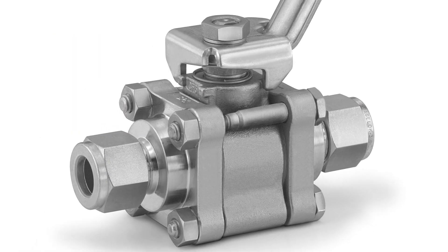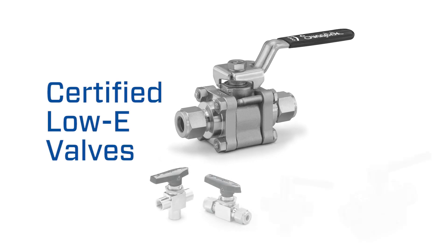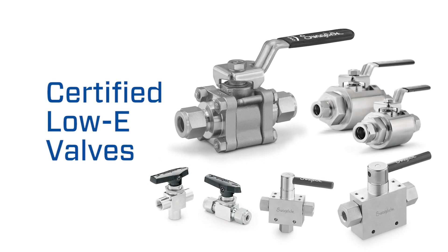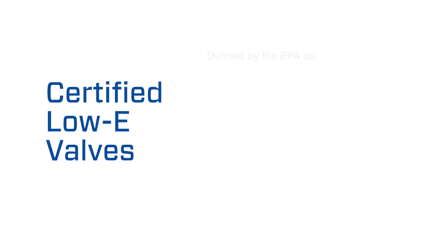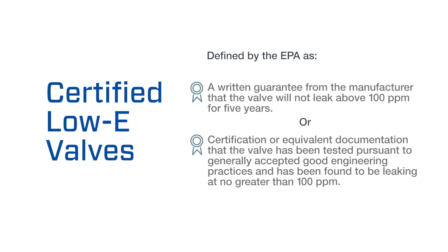These emissions can be prevented by replacing leaking valves with certified low-e valves. The EPA defines low-e valves in two ways: the first is that the valve comes with a written guarantee from the manufacturer that the valve will not leak above 100 parts per million for five years. The second is certification or equivalent documentation that the valve has been tested pursuant to generally accepted good engineering practices in good faith, duplicating process conditions and leaking at no greater than 100 parts per million.